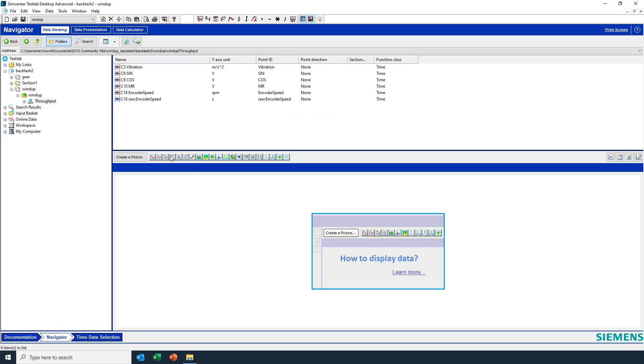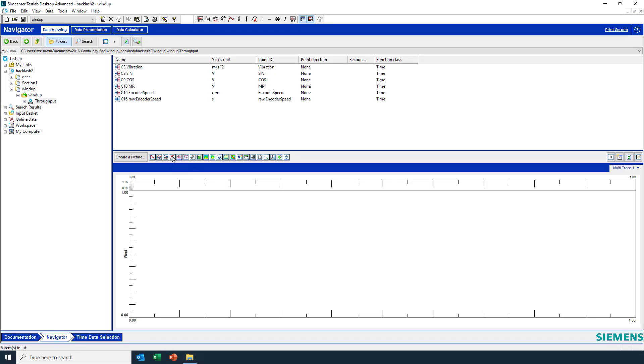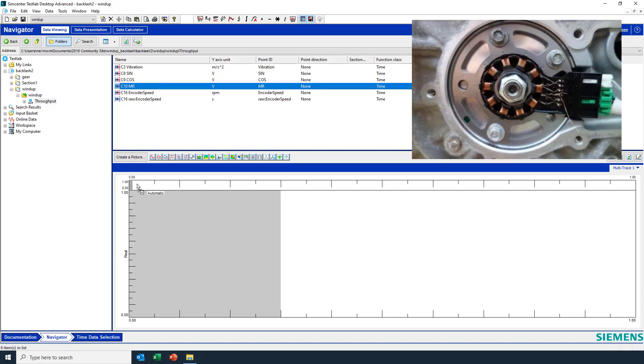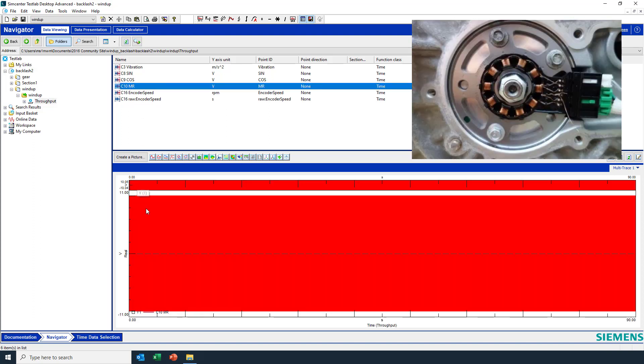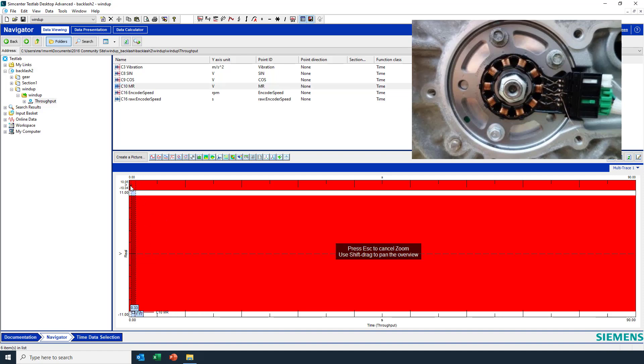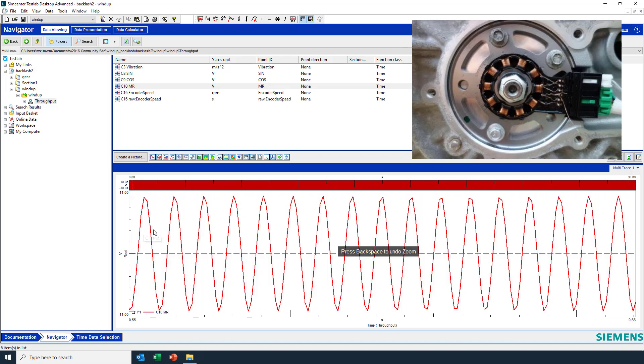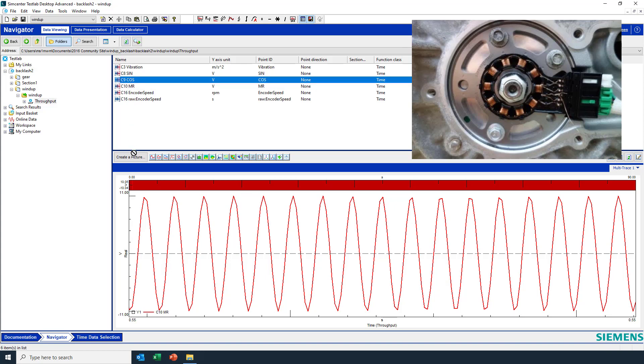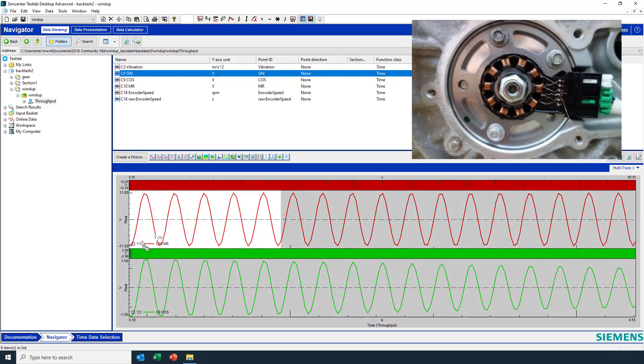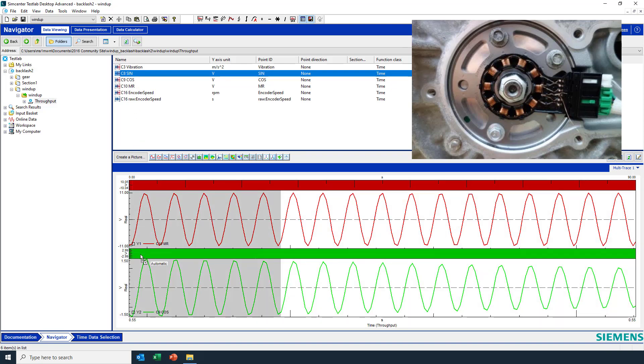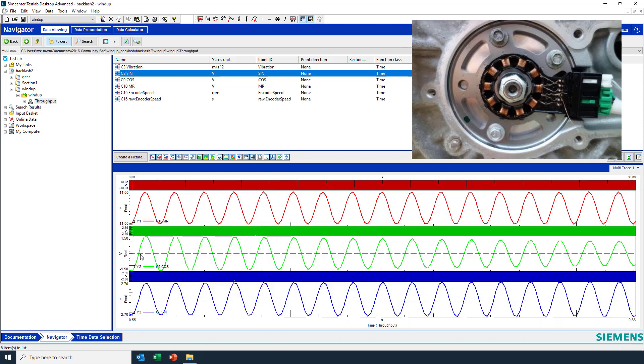Here's some of the data. I'm going to open a multi-trace display. What we have here is the resolver data. If we look in on this data we can see that this is sinusoidal data voltage, and that is the excitation to the resolver. There is also a cosine and a sine wave that come out of the resolver, and I can plot those as well here.